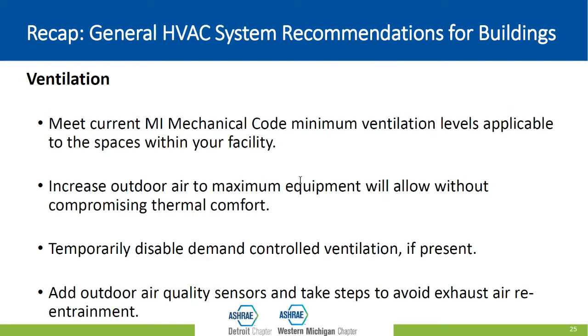If you happen to have demand control ventilation in your facility, you may, during this time, wish to disable it, right? Because demand control ventilation is going to reduce the amount of outside air that you bring in based on occupancy. And it's going to be looking at, okay, how many people are in this space at this particular time, and how much outside air do I need to bring in for this number of people? Because we want to increase our ventilation, we want to bring in more outside air. Right, so you want to disable that demand controlled ventilation, and then you also want to make sure that you've taken steps to avoid air re-entrainment. Once you've exhausted dirty, foul, used up air out of your building, you want to make sure that you don't bring that air right back into your building.